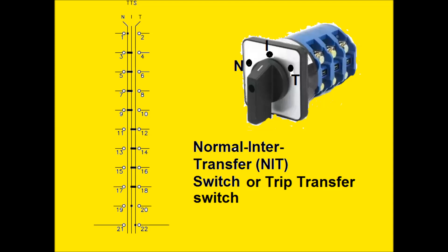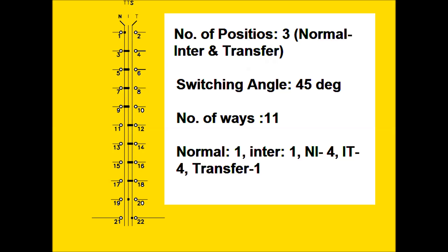Hello friends, today we will discuss the NIT switch — Normal-Inter-Transfer switch. It is sometimes called a trip transfer switch. In the NIT switch there are three positions: Normal, Inter, and Transfer. The switching angle between Normal and Inter is 45 degrees, and again between Inter and Transfer is 45 degrees. In Normal position there is one contact, in Inter position there is one contact, in Normal-Inter position there are four contacts, in Inter-Transfer position there are four contacts, and in Transfer position there is one contact.